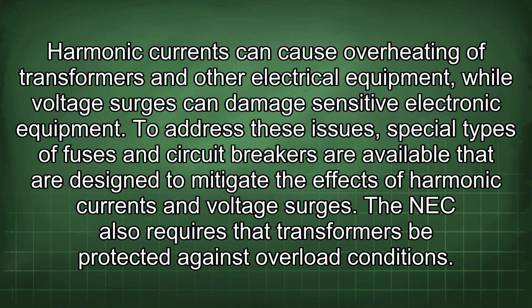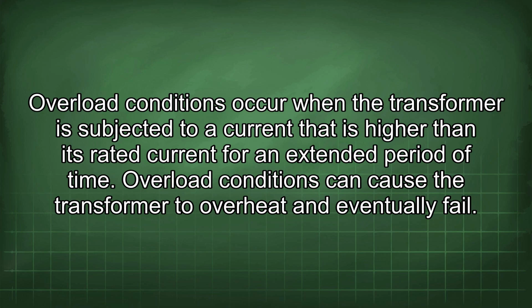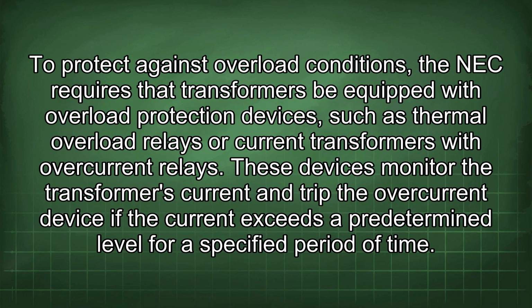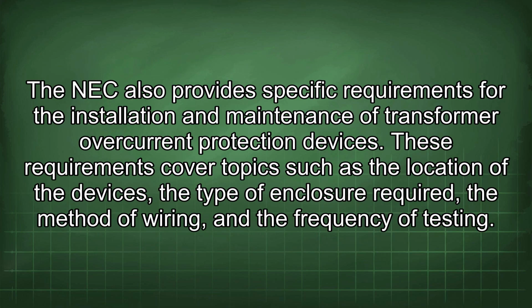The NEC also requires that transformers be protected against overload conditions. Overload conditions occur when the transformer is subjected to a current that is higher than its rated current for an extended period of time. Overload conditions can cause the transformer to overheat and eventually fail. To protect against overload conditions, the NEC requires that transformers be equipped with overload protection devices, such as thermal overload relays or current transformers with overcurrent relays. These devices monitor the transformer's current and trip the overcurrent device if the current exceeds a predetermined level for a specified period of time.